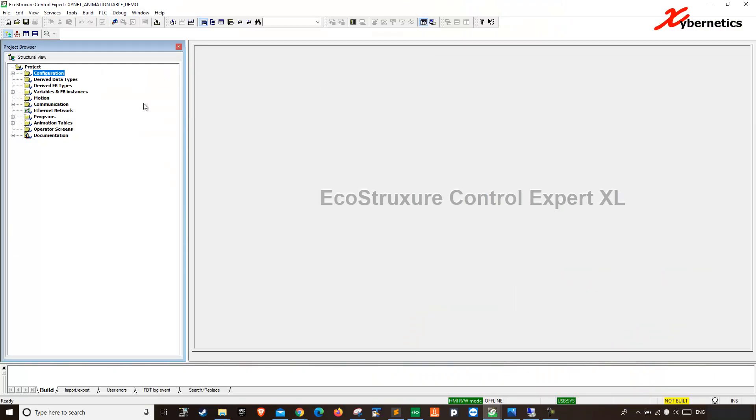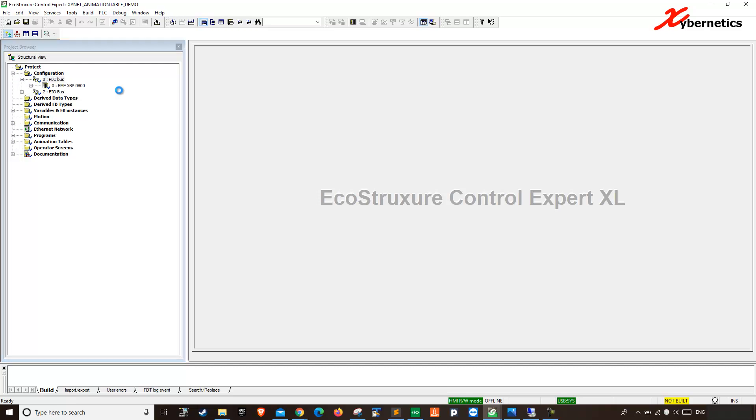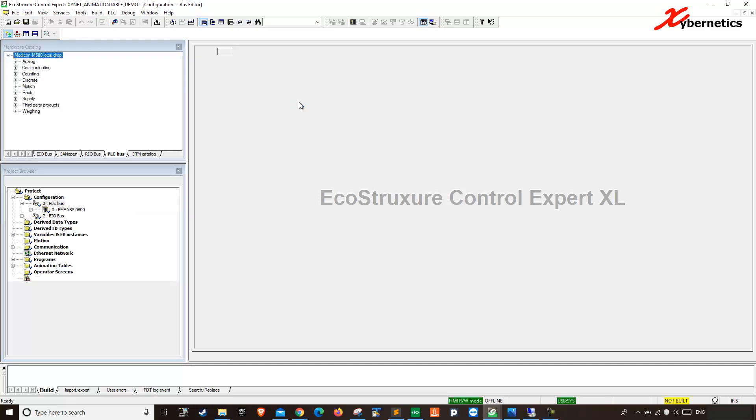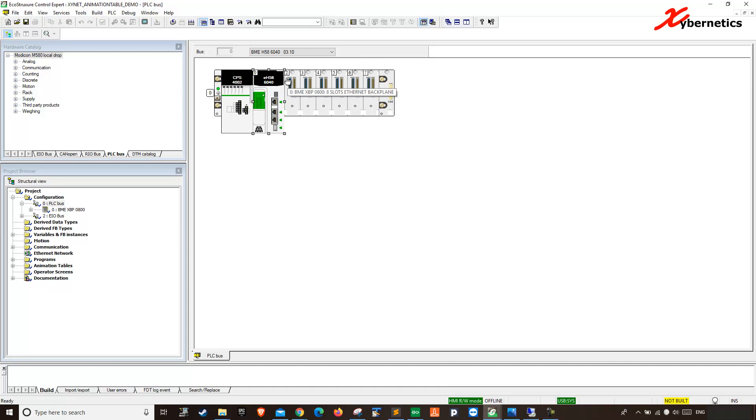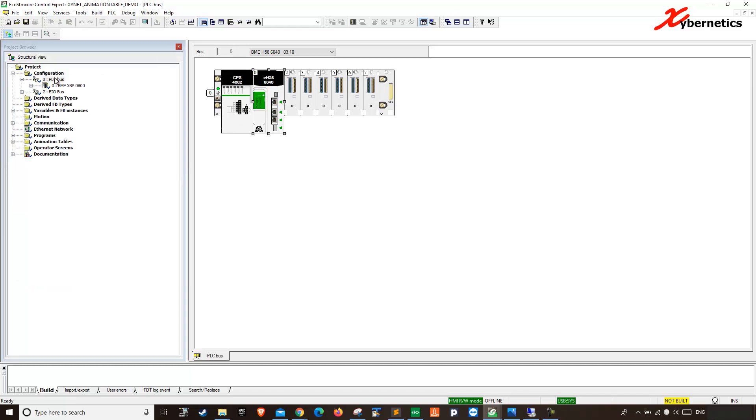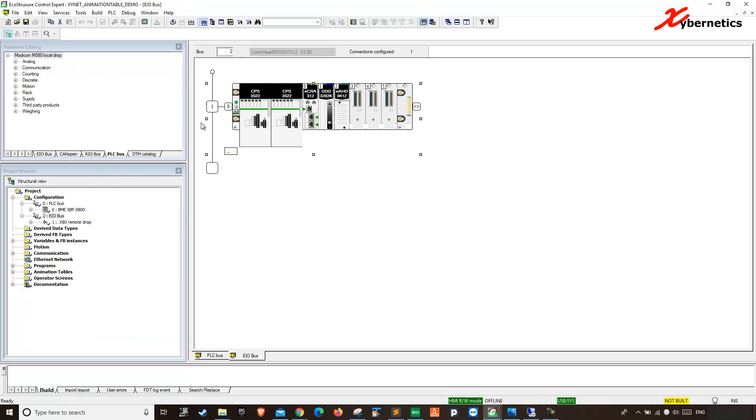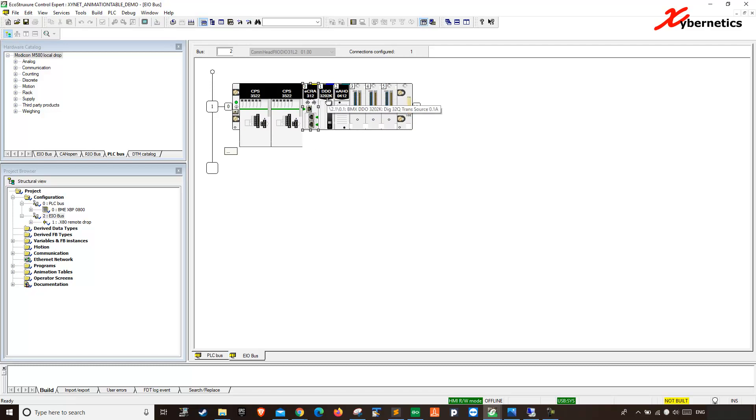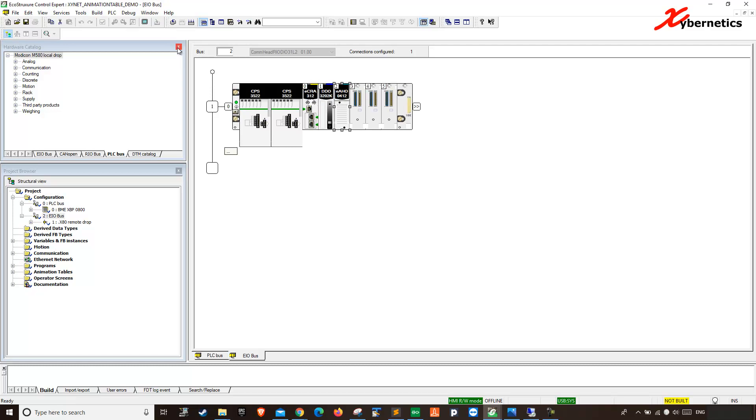I've got an M580 program here. This is your PLC bus. It will have one power supply with a hot standby CPU. It's got eight slot rack. The main IOs are on your remote IOs on the EIO bus. If you double click this guy here, it will show you what you have on your remote IOs. It's got two power supply, redundant power supply with one Ethernet module for communication. On slot one you have a DO card and slot two you have an AO card.